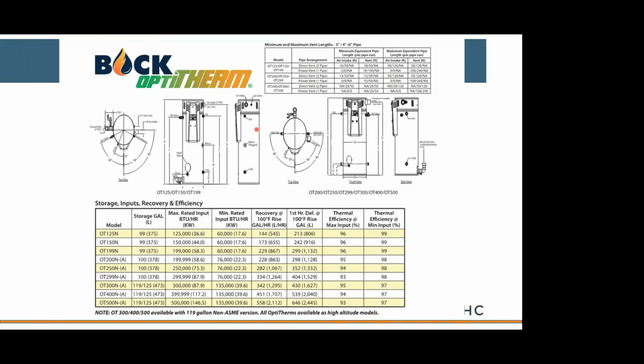A lot of people ask or maybe get confused by how do you physically size a water heater? So let's talk real quick about a tank type and maybe demystify it a little bit. There's a lot of information on a standard submittal or selection sheet that you might have to decipher a little bit. As far as what size burner you've got, how much storage is available, the efficiencies, is it modulating? And then you've got recovery rates.